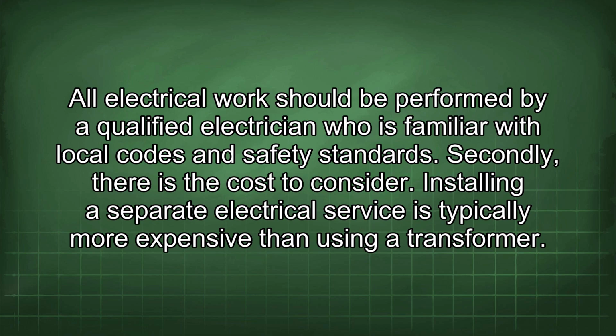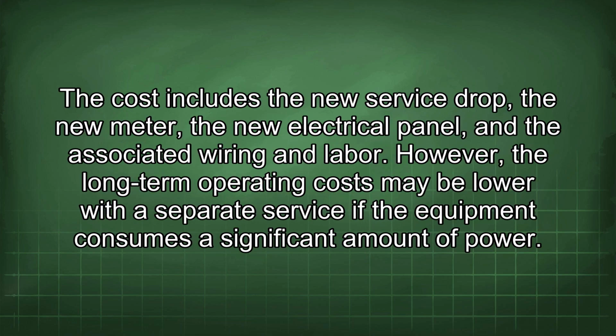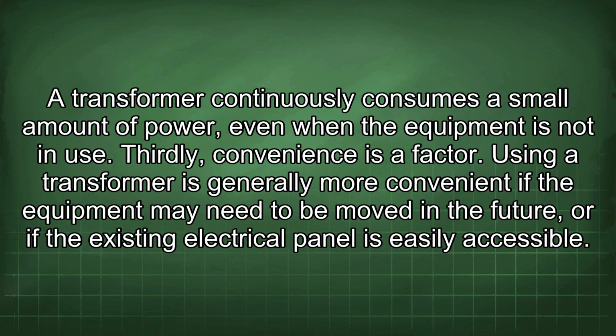Secondly, there is the cost to consider. Installing a separate electrical service is typically more expensive than using a transformer. The cost includes the new service drop, the new meter, the new electrical panel, and the associated wiring and labor. However, the long-term operating costs may be lower with a separate service if the equipment consumes a significant amount of power. A transformer continuously consumes a small amount of power, even when the equipment is not in use.